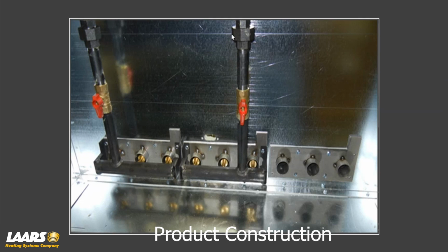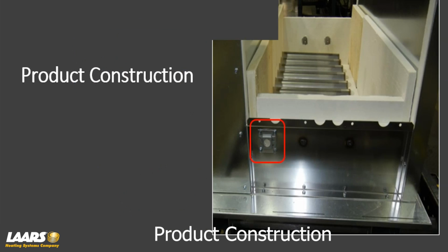On CSD1 products, you'll also have a union and a shutoff valve. So if you ever had to take them out, you could break the union, remove your 4 stainless steel screws for the manifold, pull that out, and then remove the 4 stainless steel screws for the burner and slide those out. If you're non-CSD1, you will not have the union in the lower deck. That comes up through the upper deck, and you would have to disconnect that from the bottom half of the gas valve, which is held into place with Allen screws.